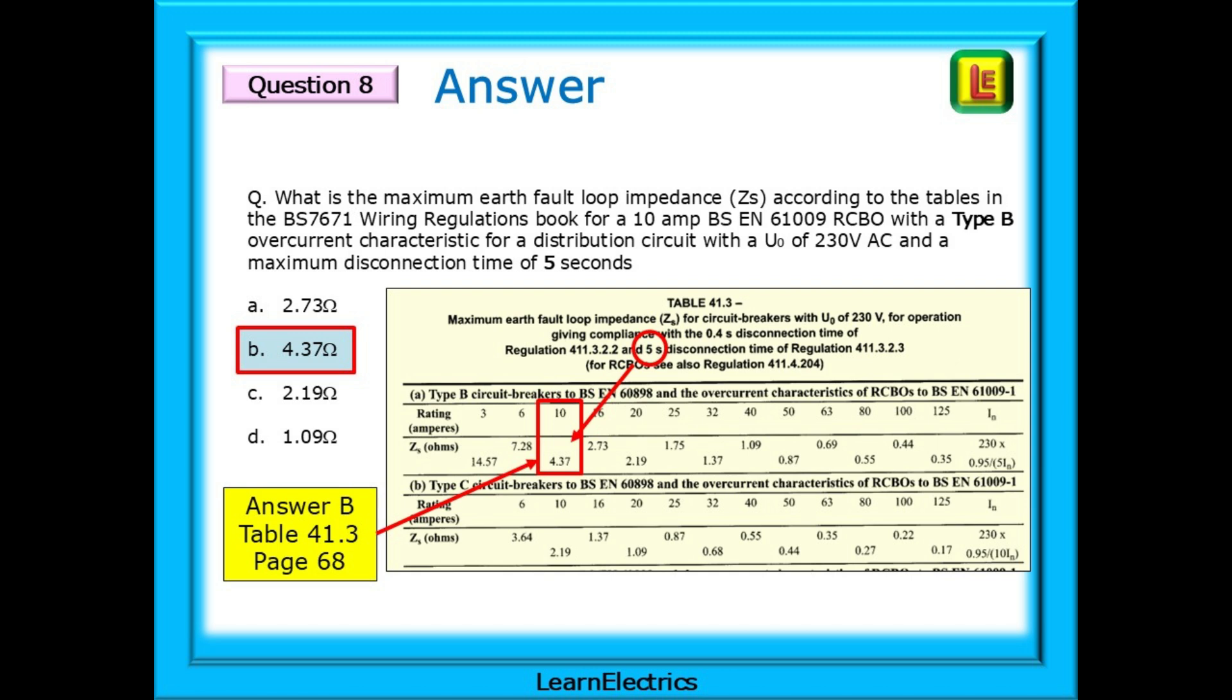You need to know that for BS EN 60898 circuit breakers and BS EN 61009 RCBOs, the ZS values for final circuits and distribution circuits are the same. They both use table 41.3.